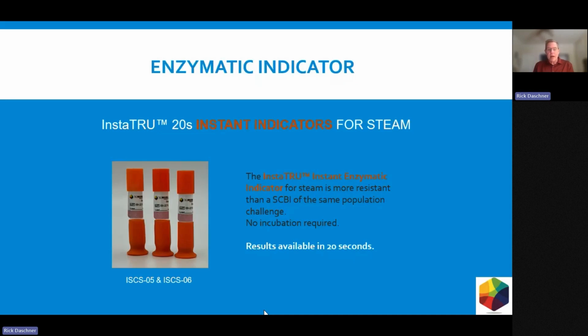And just to give you an idea of how it works, you would put that into a load, and when you pull it out, you add a coenzyme to a tablet that's inside, and within 20 seconds, you get a validation result that yes, it passed, or no, it didn't. It doesn't require any incubation. And the beauty of this is that it can be done anywhere within a facility. You don't have to run and find an incubator or take it to a lab or send it somewhere. It can be done on site.